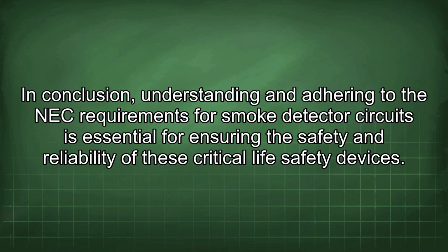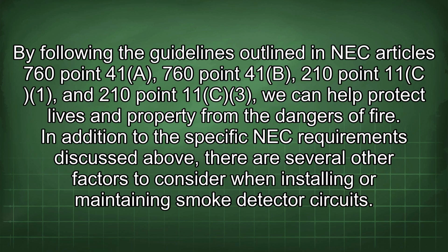In conclusion, understanding and adhering to the NEC requirements for smoke detector circuits is essential for ensuring the safety and reliability of these critical life safety devices. By following the guidelines outlined in NEC Article 760.41a, 760.41b, 210.11 c1, and 210.11c3, we can help protect lives and property from the dangers of fire.